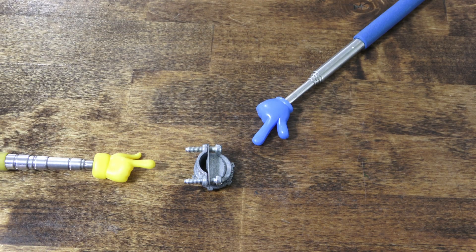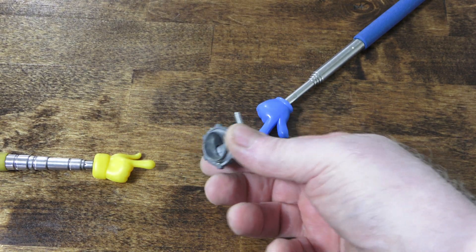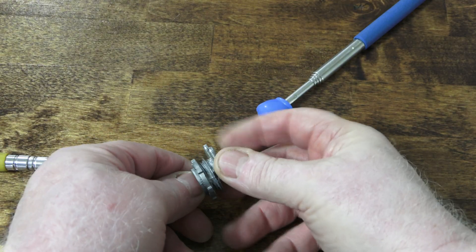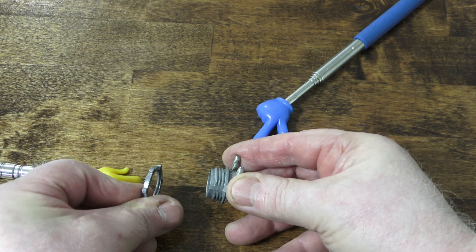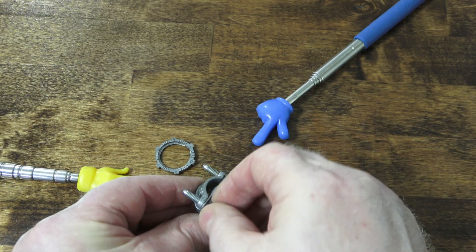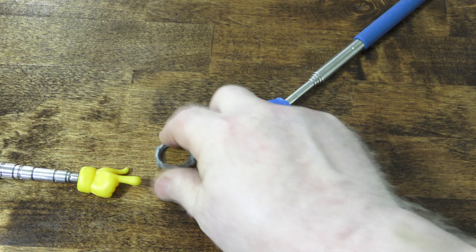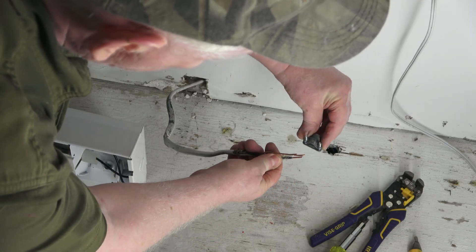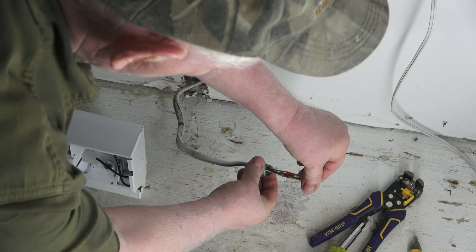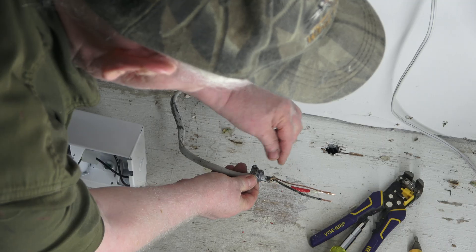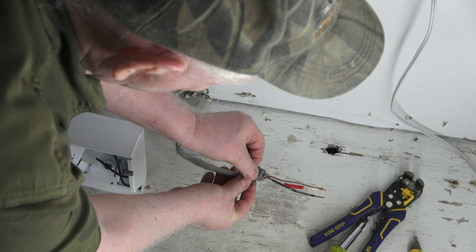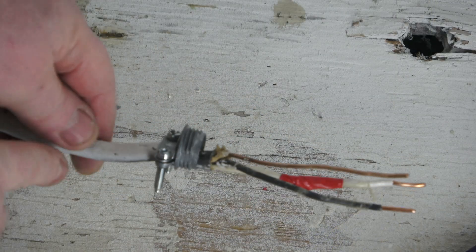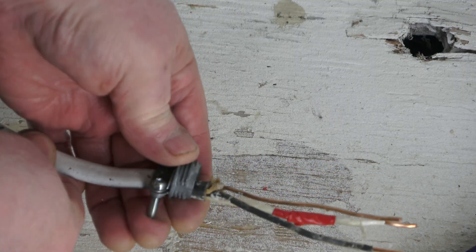So here I have a Romex connector. That's what they're commonly called. I'm trying to use electrical terms. So when you go to the hardware store, they'll know what you're talking about. So you spin this off. And then this will sandwich in between the unit. Pull this back. You can loosen these more. Get more width to get the wire through. You're hanging upside down. It stays open. And you bring your wires through. And it slides over the sheathing here. And you only need half inch or less showing. And then you tighten these down. Threads facing outward. Snug is sufficient. You don't want to go Superman type because this is metal and wire doesn't move.